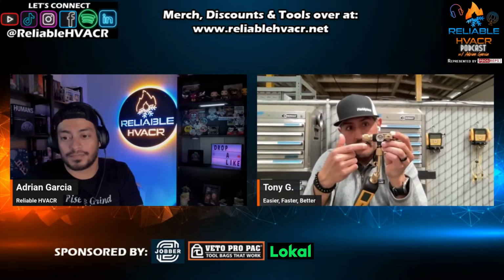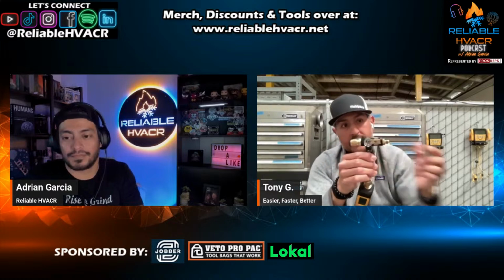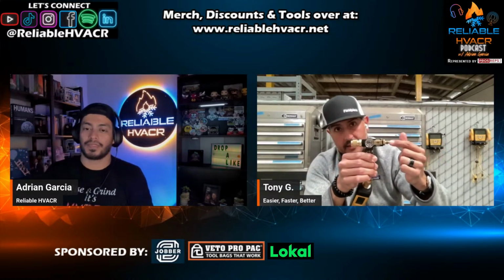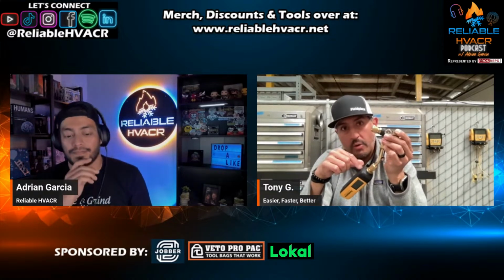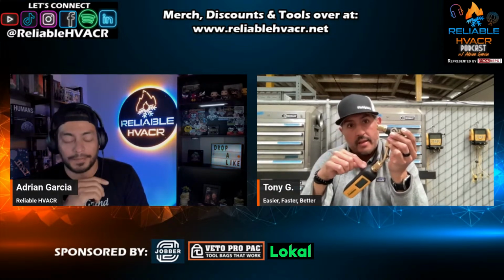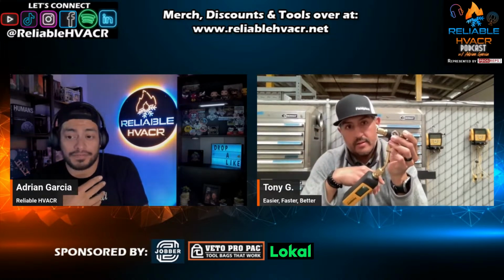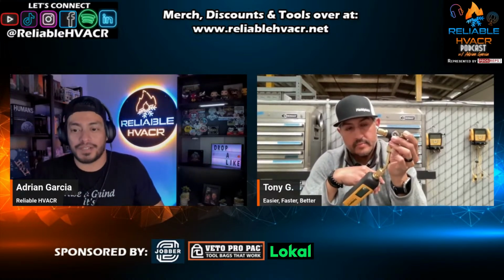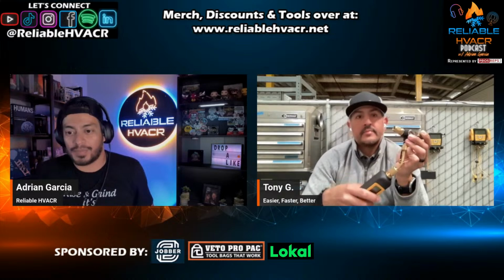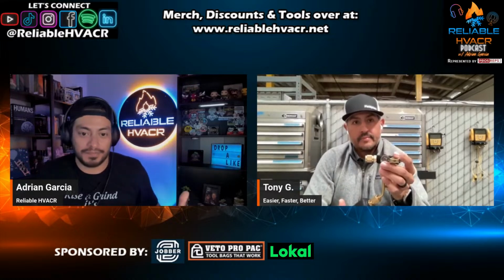And the issue is that when you're done with your evacuation and it's time to charge refrigerant back into the system, you don't want to expose your micron gauge to refrigerant or to high positive pressure. Right? Yeah, I've heard people have issues with that. Sometimes you just open the valves, and most micron gauges can take that positive pressure, but you get oil in there, you get something else in there, and then you got to deal with that. You got to dry it out, clean it out. Something could happen.